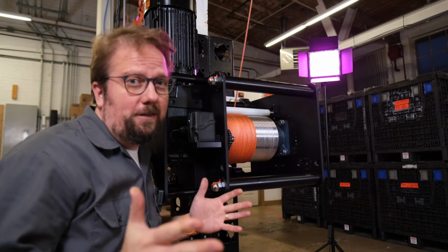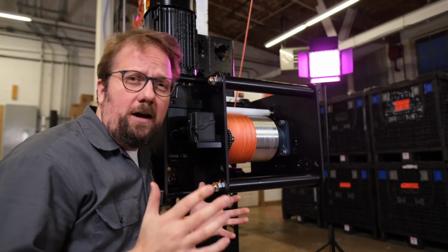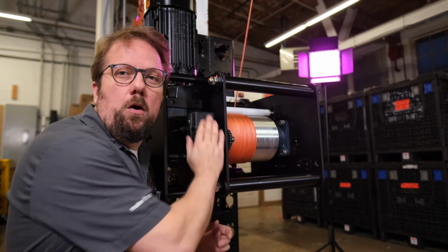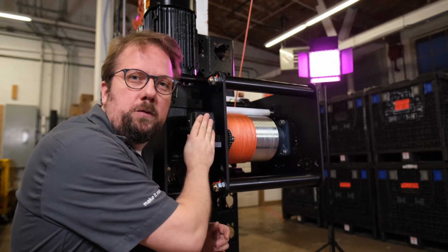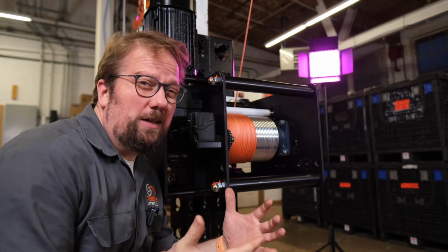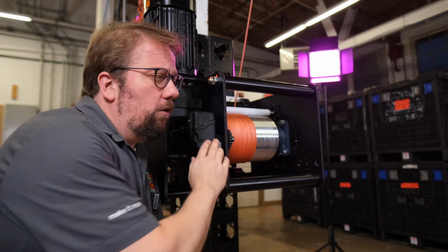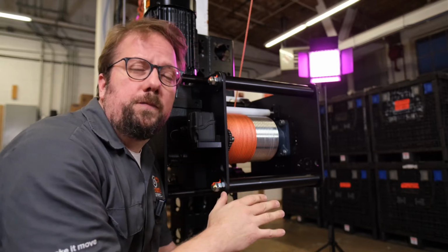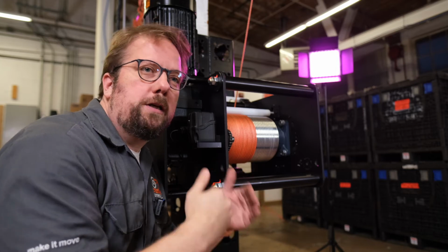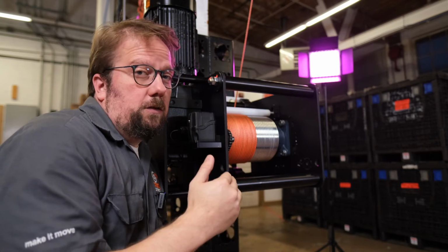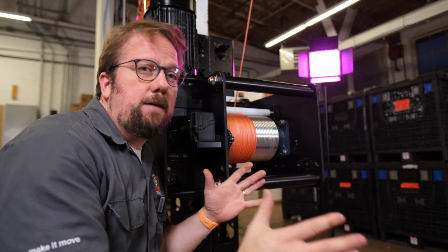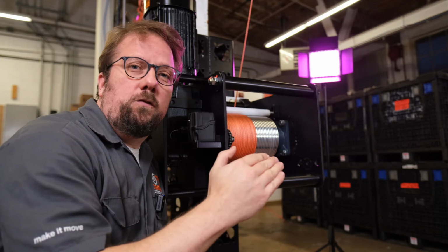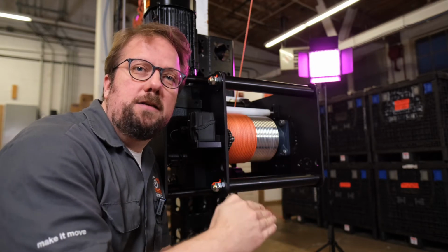Okay, I hear you. You're saying, Gareth, we're converts. We want to set our limit switches. I'm so happy to hear it. But when? When should we open that box and when should we set them? Well, pretty much as soon as you possibly can. These are low-level sensors that don't rely on the motion controller or the computer, so you really want to set them early in the process. Once your hoist is rigged and everything looks set mechanically, you should get your limit switches set, because everything from that stage forward, you want to have that protection in place.